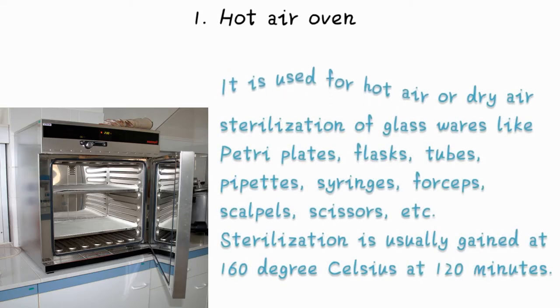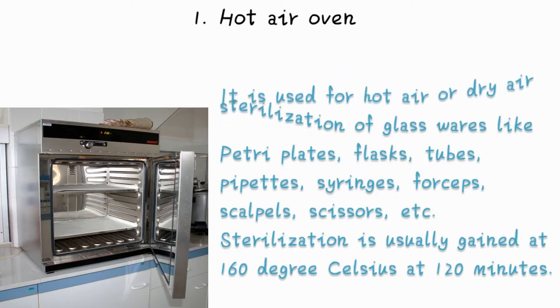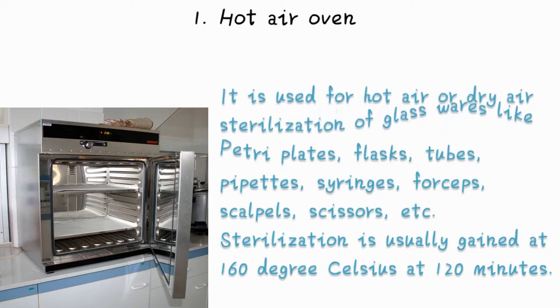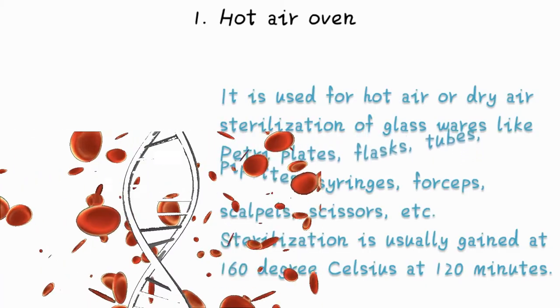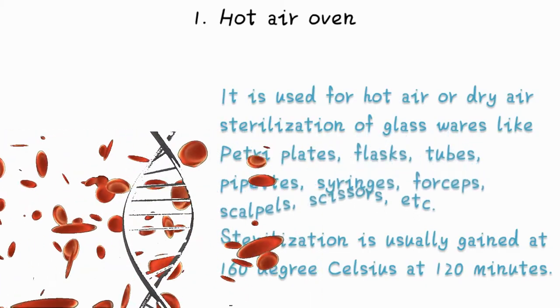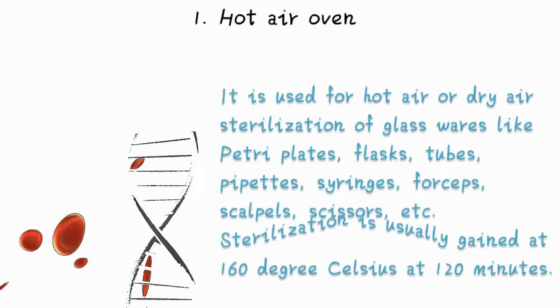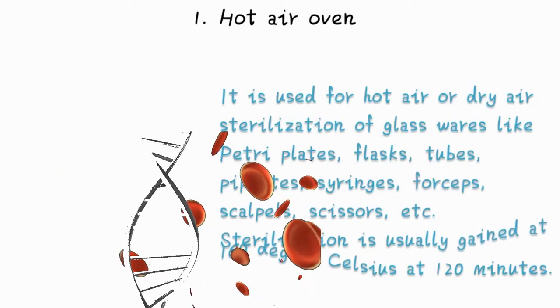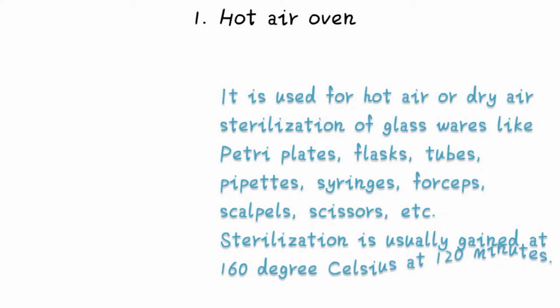Hot Air Oven. It is used for hot air or dry air sterilization of glasswares like petri plates, flasks, tubes, pipettes, syringes, forceps, scalpels, scissors, etc. Sterilization is usually gained at 160 degrees Celsius at 120 minutes.